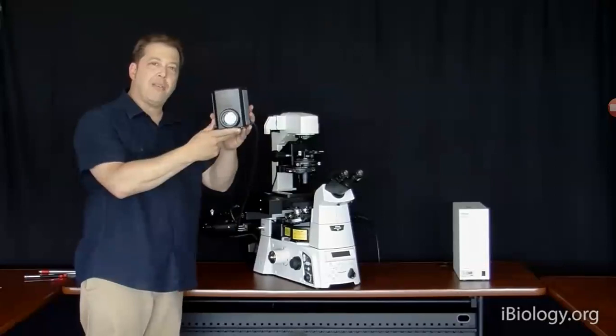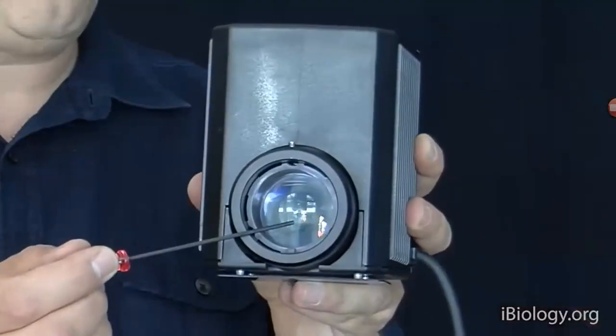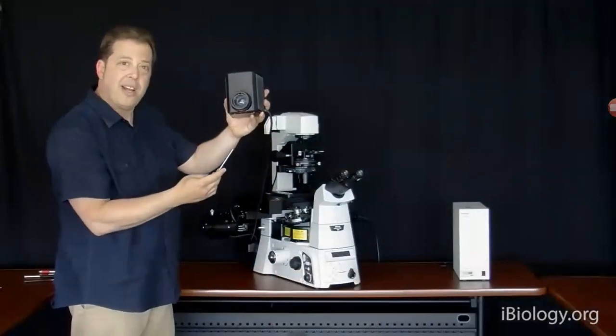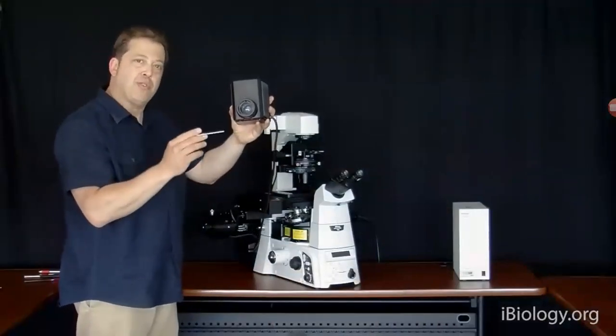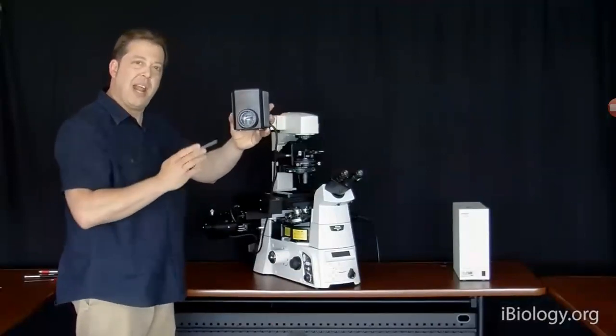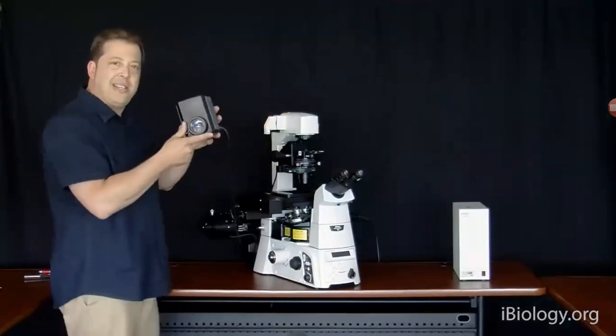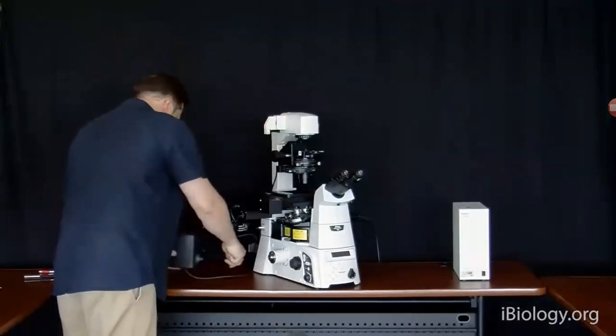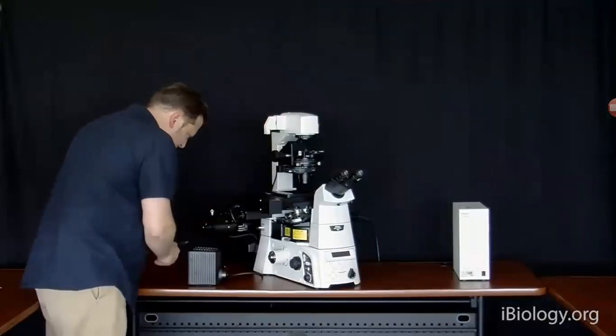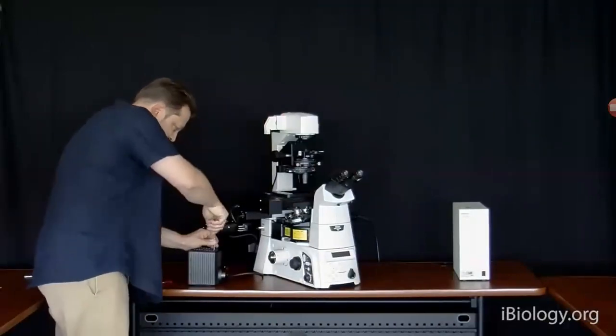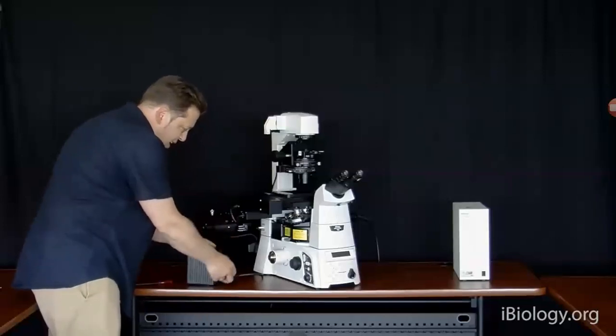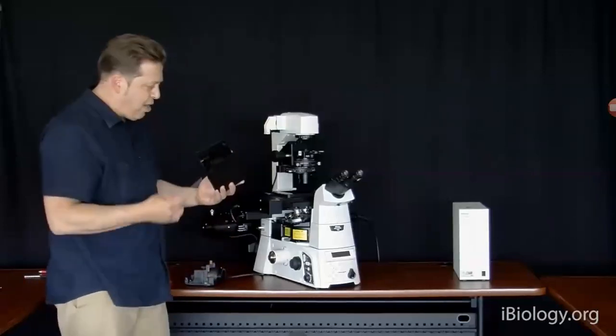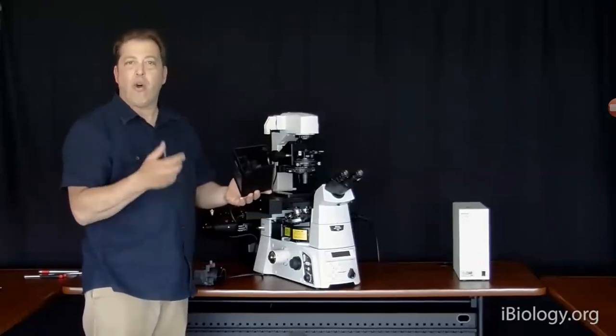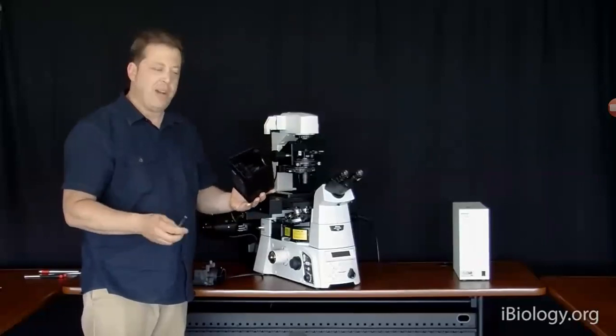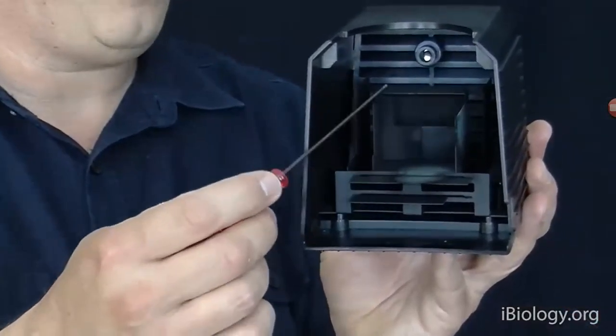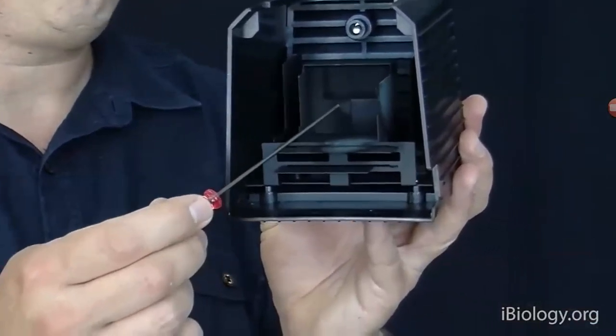So this is your halogen lamp house on the microscope, and you can see there's a collector lens in here, and you can see a magnified image of the first aperture plane, which is the filament inside that halogen bulb. If we were going to take that bulb out of here, we would do that by removing this insulated cover, which is very heavily shielded because the bulbs, if they have oil on them or overheat, can actually explode. It's extremely rare, but it happens. But for that, you need to have everything shielded with heavy metal inside the cover of the lamp.